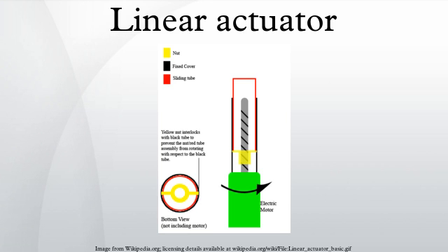In some cases, high viscosity grease can be added to linear screw actuators to increase the static load. Some manufacturers use this to alter the load for specific needs. Static load capacity can be added to a linear screw actuator using an electromagnetic brake system, which applies friction to the spinning drive nut. For example, a spring may be used to apply brake pads to the drive nut, holding it in position when power is turned off.